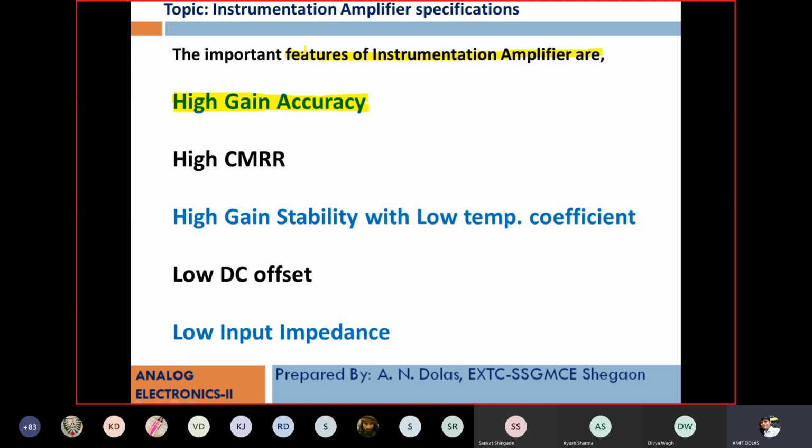And by putting such a passive component into a Wheatstone bridge along with some active element, proportional current, voltage, or power can be developed, and it may be amplified with the help of an amplifier. As the output of such transducers is very low, maybe in microvolt or millivolt, thereby we need high gain and it must be accurate so that the reading will be accurate.